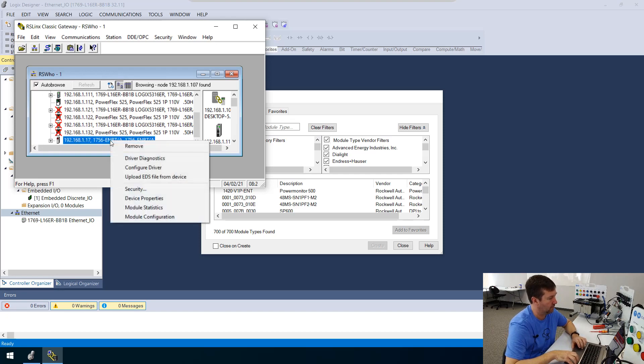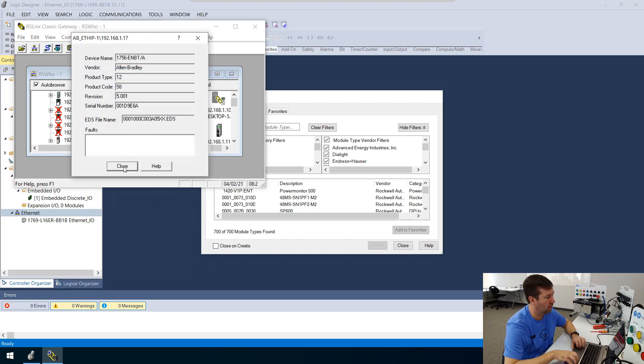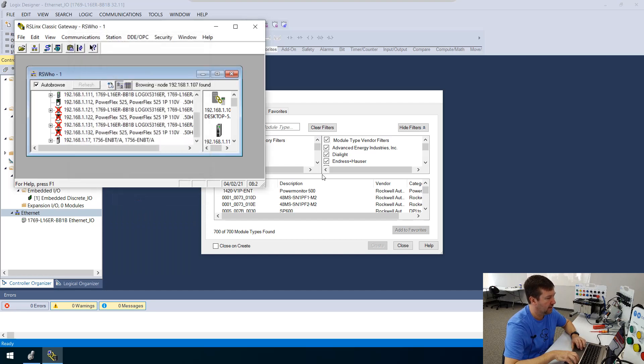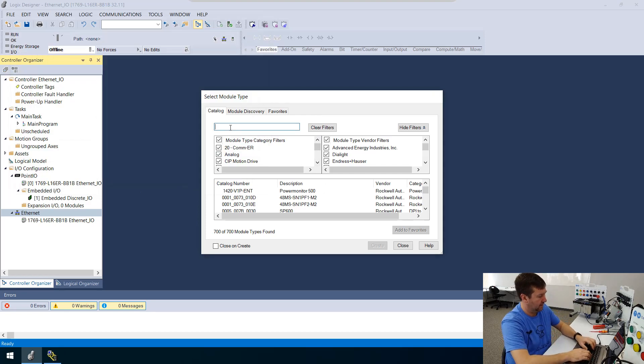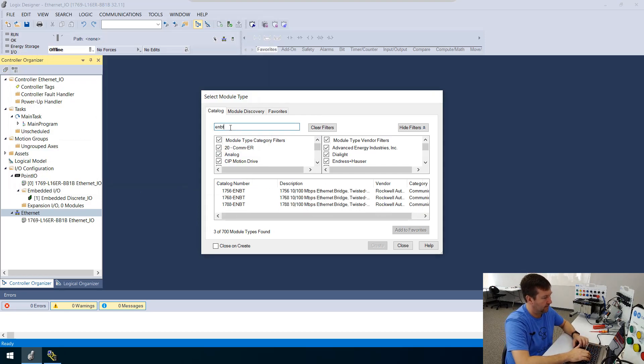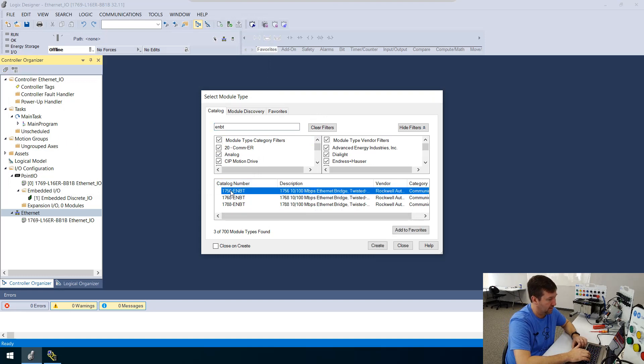we see that it is a 1756 ENBT. And we can right-click it and we can see the device properties and see that it is revision 5.001. So in Studio 5000, let's type ENBT. And there is the 1756 ENBT. So we're going to select it and create.